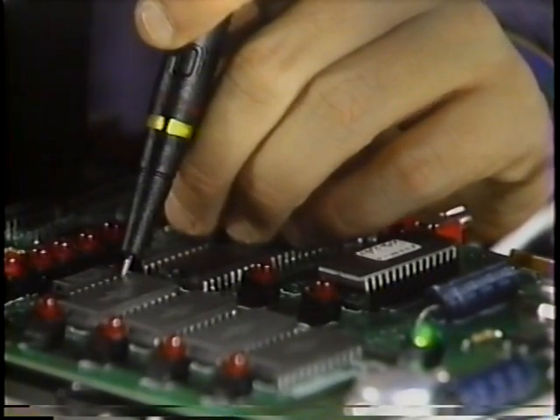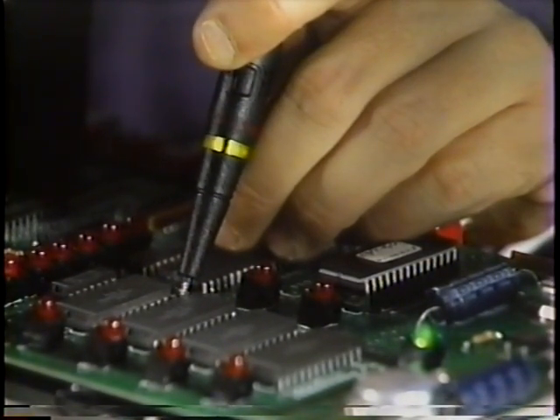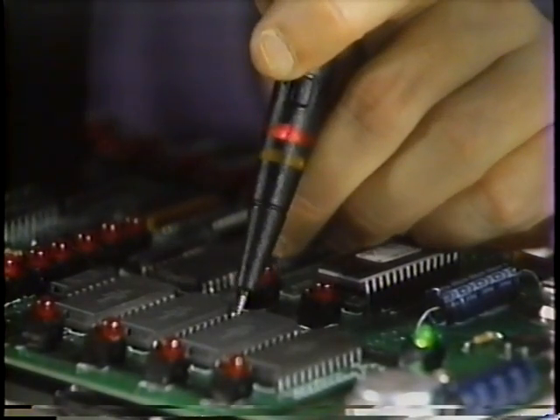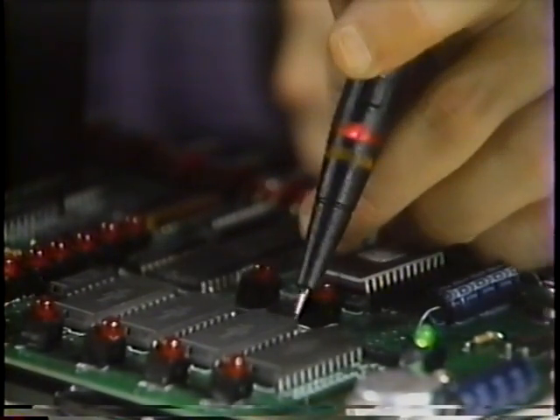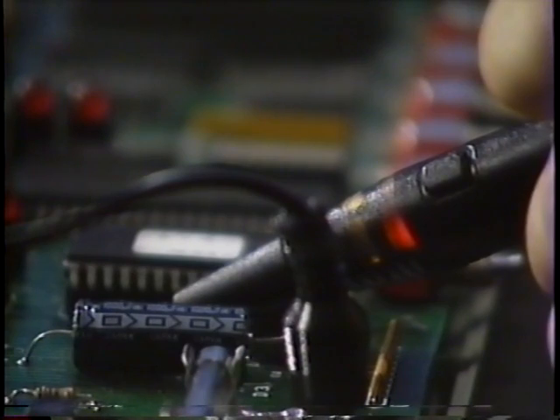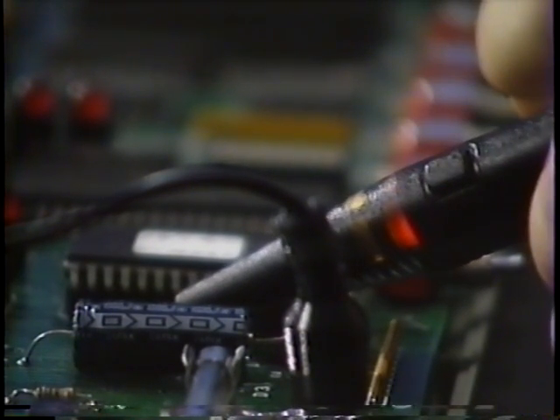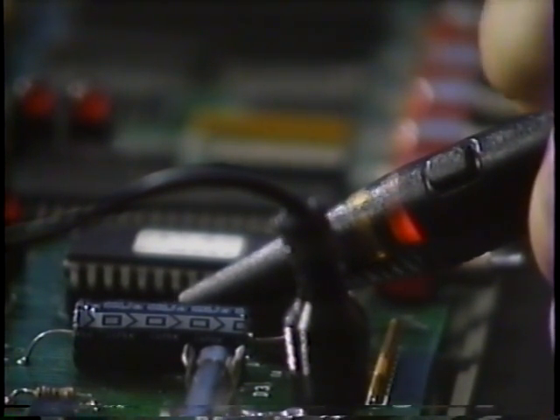The probe lights will also toggle when the selected line is probed, so you can run these tests without looking at the display. Particularly handy when you are working in cramped quarters. Press the probe push button or the Enter key to increment to the next higher line.